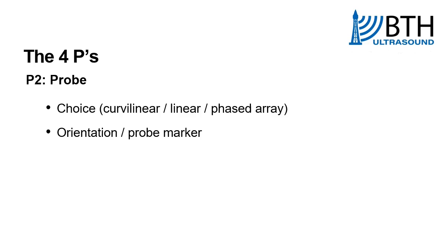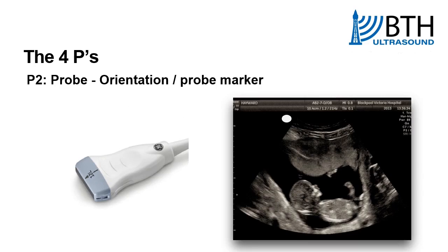There is an orientation and probe marker on every transducer probe. These can be found on the side, and they should correlate and line up with the image on the screen, so you know which side of the patient and the probe you are scanning in what orientation. There's a standard method to keep this consistent, particularly when you're trying to record images for somebody else to view, so that they know where you are scanning with regards to the patient's anatomy.